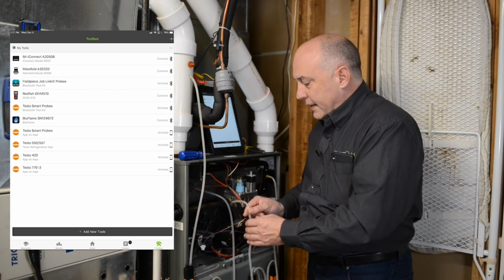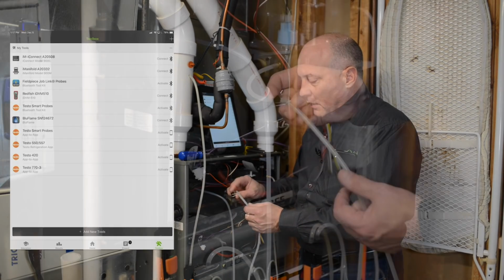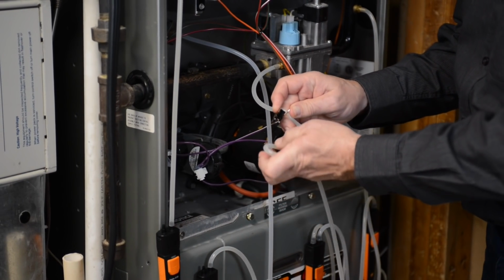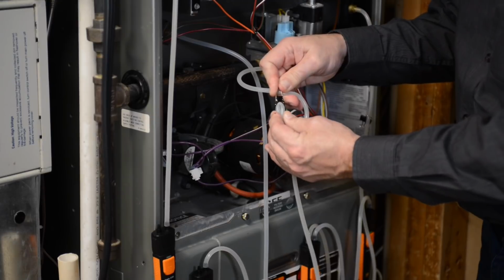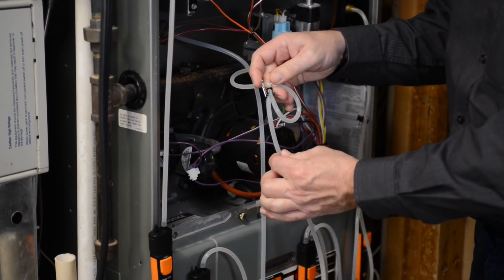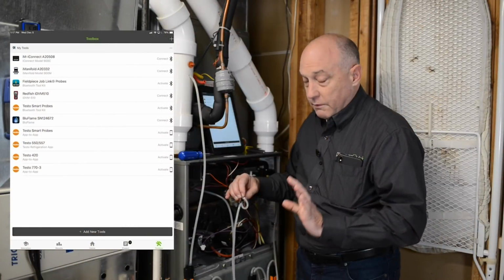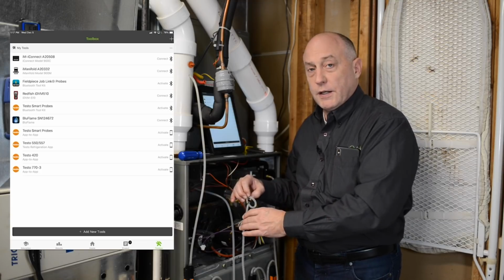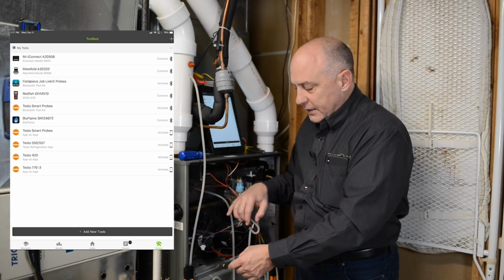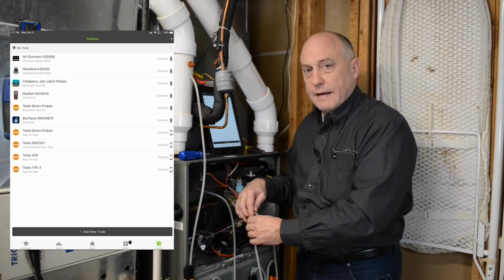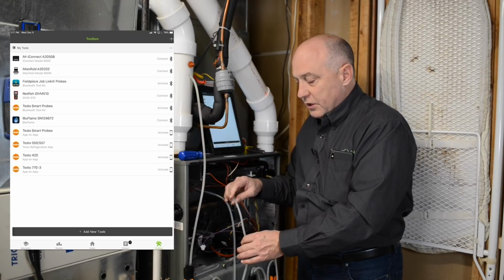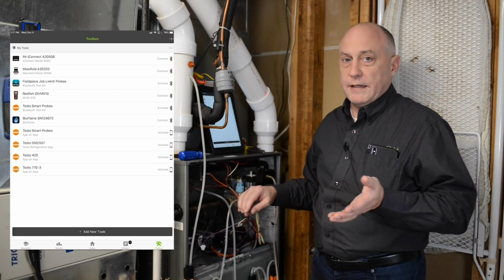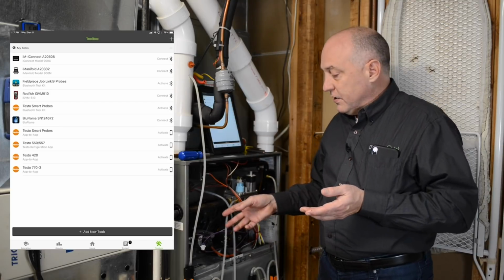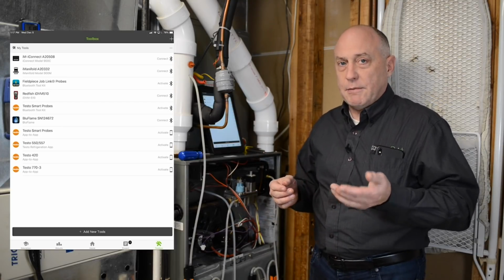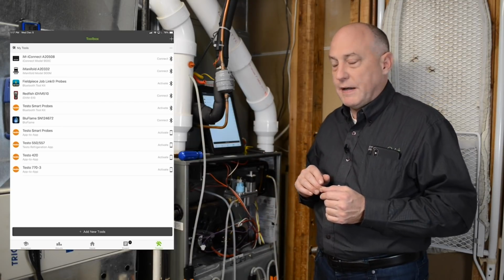Now, another cool thing I did on these was I put a small clip on here so that if I want to zero my manometers out, I can literally just fold my hose in two, open up this clip and clip it on here, and now the clip has this sealed off so I don't have pressure on here. And when I take the hose off and zero the manometer, I can do that very easily. So just a little quick tip, especially with gas, where on the inlet side you have gas pressure all the time. It makes it really easy to zero the manometers if you have to.